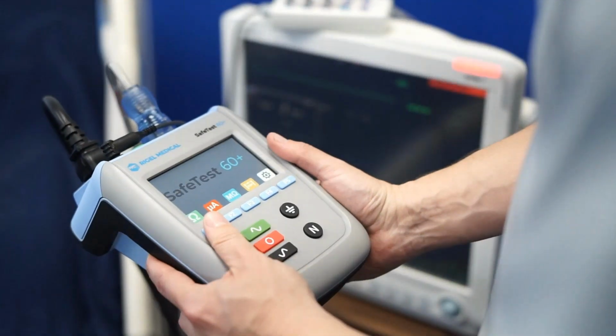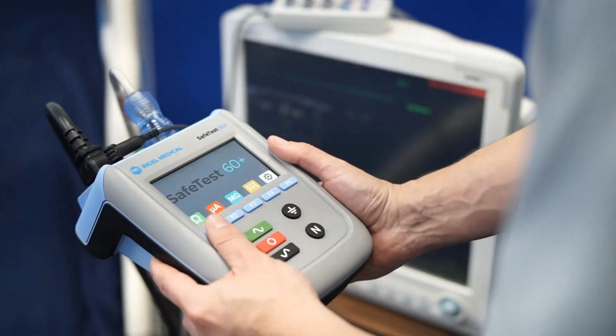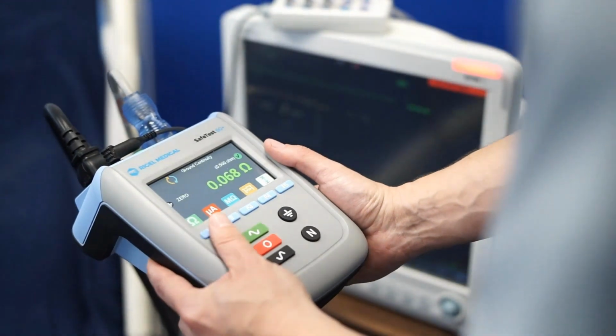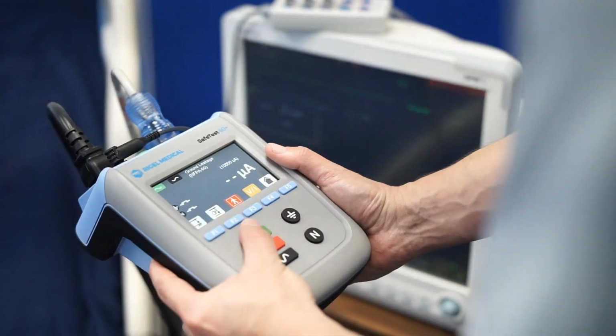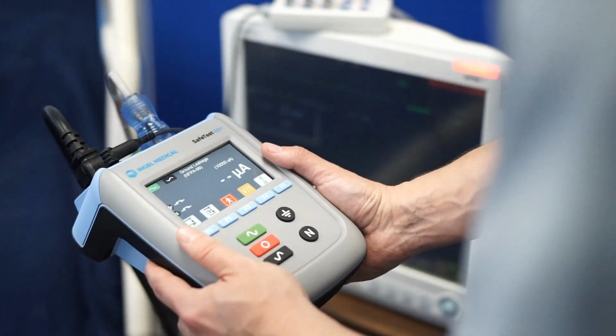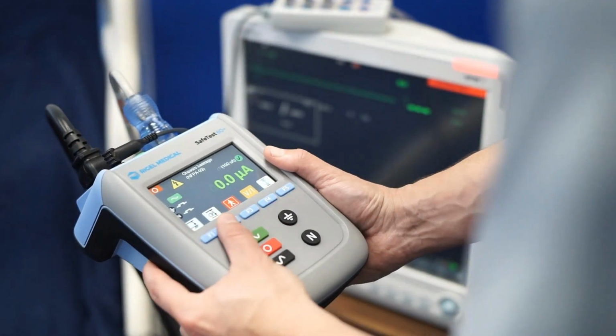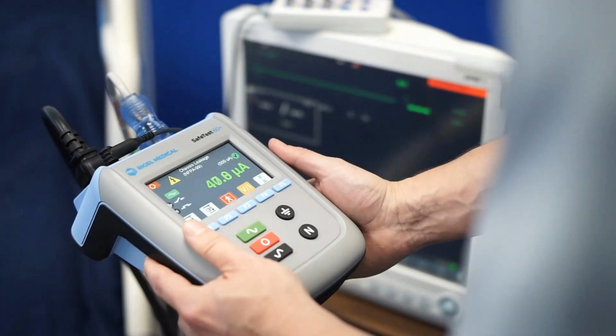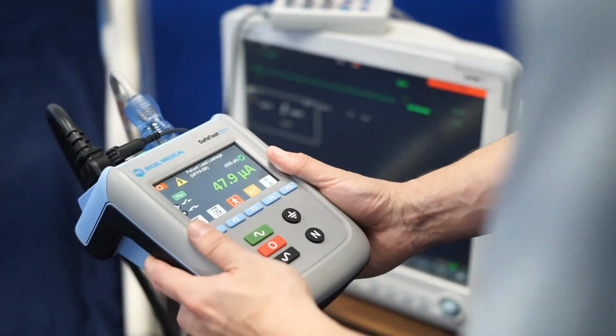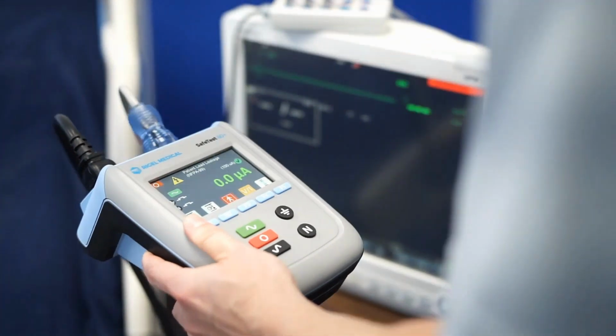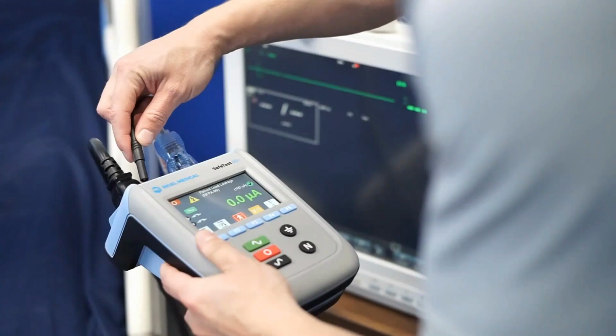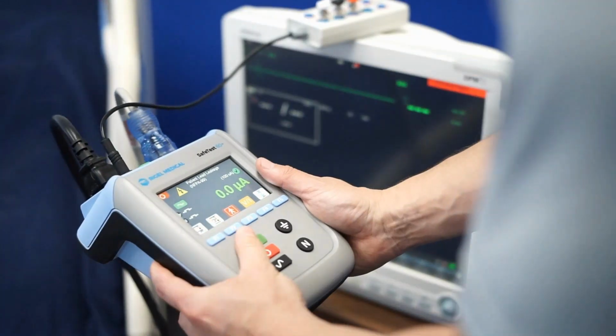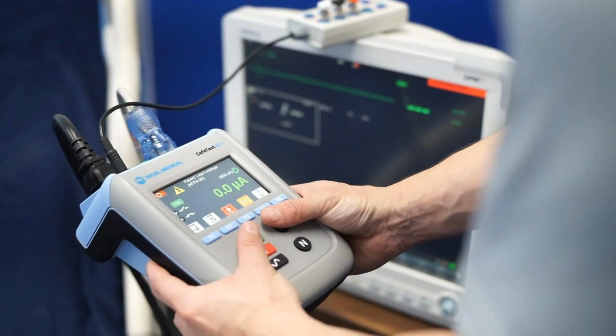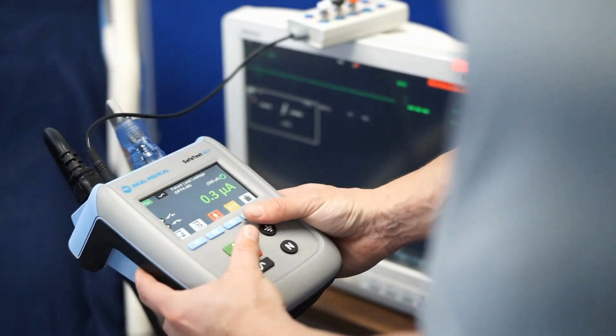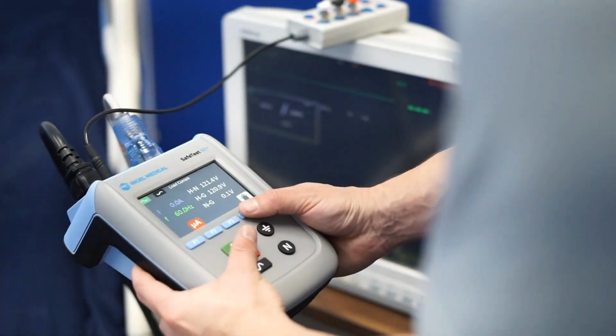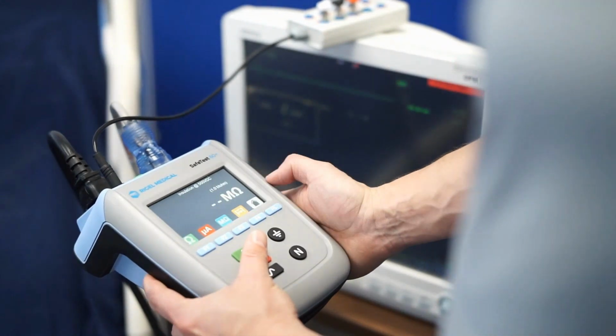So we can see from when we first turn the device on, we can select ground bond at the far left-hand side. From there, we can perform a ground continuity test from the probe. That's a pass, it's under 500 milliohms. From there, we can perform a ground leakage test by pressing the green button. As long as it falls under that limit, it gives us the accurate results. And then from there, we can move across to touch leakage or chassis leakage, open ground, and then finally to patient lead leakage. From there, we switch the probe from the ground bond lead to the patient lead applied part box, and then we can take a measurement, hitting the green button again. We open the ground using the function keys, very easy to use, and then the final test is just checking the load current. So it's a very easy device if you're just running from left to right.